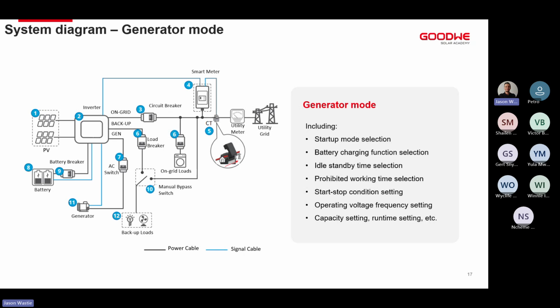And when running it through the generator ports, we can configure the generator to run in our inverter in a few different ways. We set the rated power of the inverter, the runtime of the inverter, and then we can set things like the prohibited working hours, being times when we don't want the generator to run. So if I don't want the generator to run between 2 o'clock in the morning and 5 o'clock in the morning, I'll set the prohibited working times accordingly. And it does not matter what other settings we have set, it will not start the generator during those times.